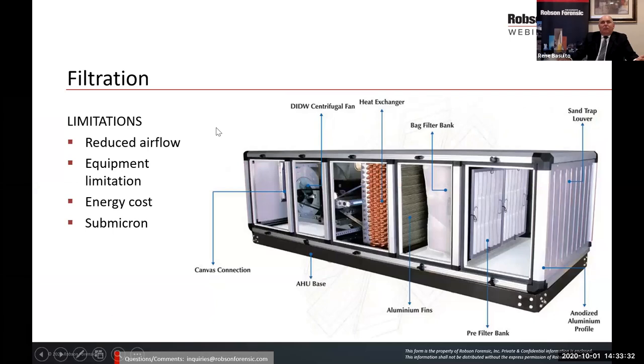And let me move this out of the way again. There we go. All right. So we go back to the limitations that we were talking about. There's a reduction in airflow because we have a much higher resistance. There are equipment limitations because you already have existing equipment where the fan and the motor that drives the fan are already sized for a particular resistance. So if you start increasing the resistance, you end up with the chance that the motor and the fans don't have the capability of moving the air that you need to move.